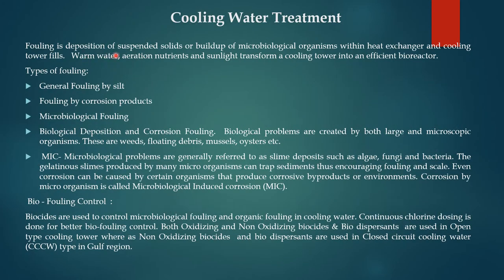Fouling is the deposition of suspended solids or build-up of microbiological organisms within heat exchangers and cooling tower fills. Warm water, aeration, nutrients, and sunlight transform a cooling tower into an efficient bioreactor. Types of fouling generally include fouling by silt, fouling by corrosion products, microbiological fouling, biological deposition and corrosion. Biological problems are created by both large and microscopic organisms.